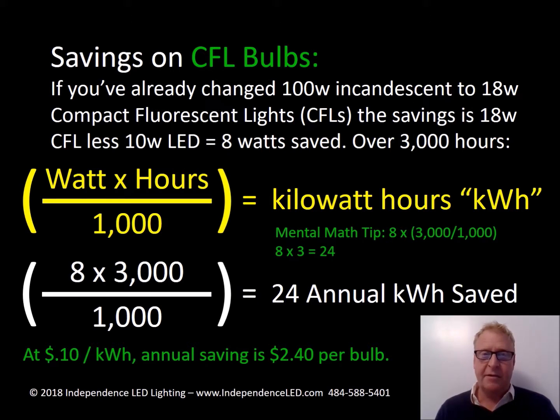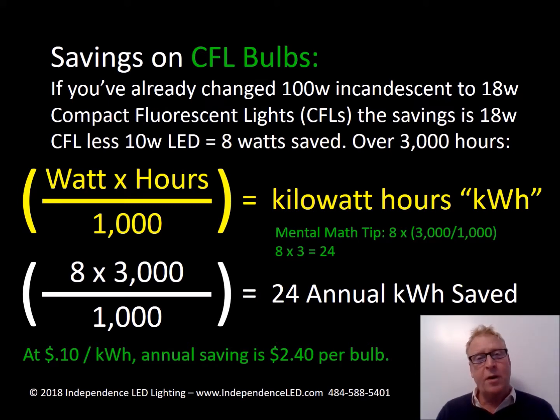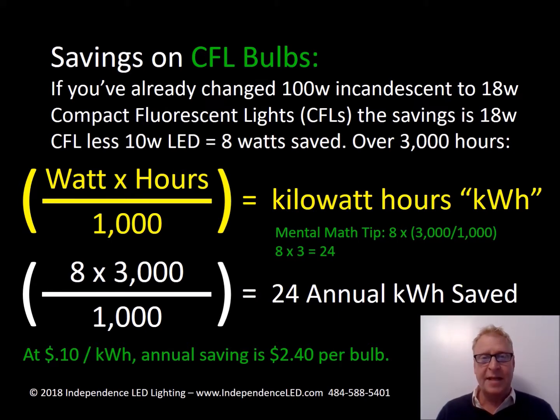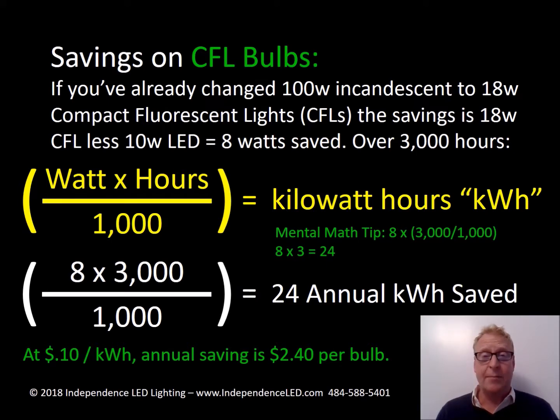Savings on CFL bulbs: you've probably changed a whole lot of incandescents to CFLs. For 100 watts, that's typically down to an 18 watt CFL. We can bring it down to just 10 watts with LEDs. 18 minus 10 leaves 8 watts saved. With the mental math and 3,000 hours, 3 times 8 is 24 kilowatt hours saved. At 10 cents, you're talking about saving $2.40 — some bulbs only cost that much. That means you get your money back in the very first year and they're going to last for well over a decade.